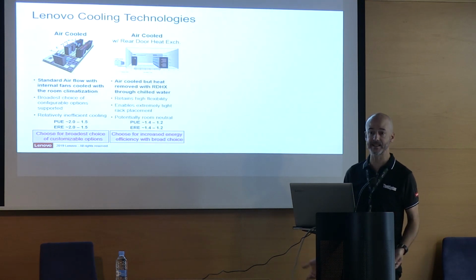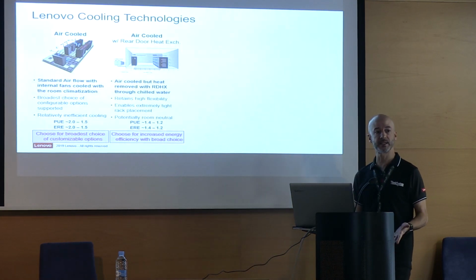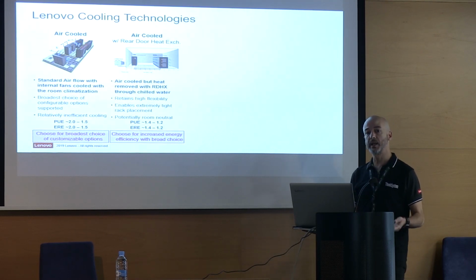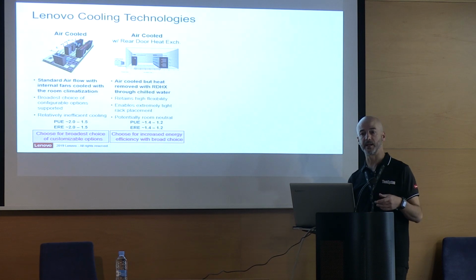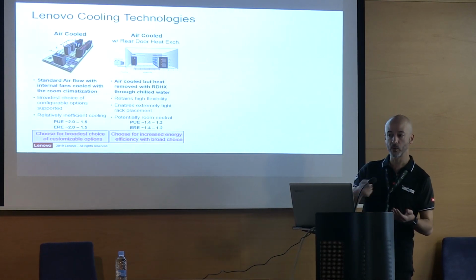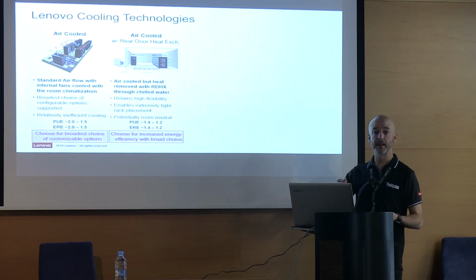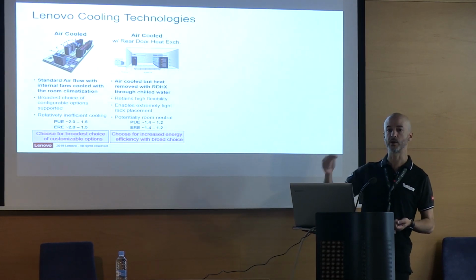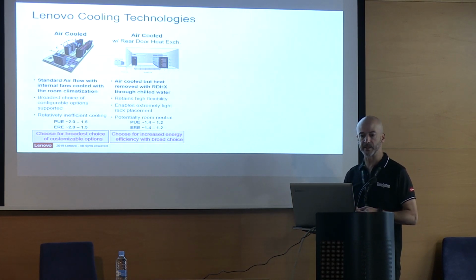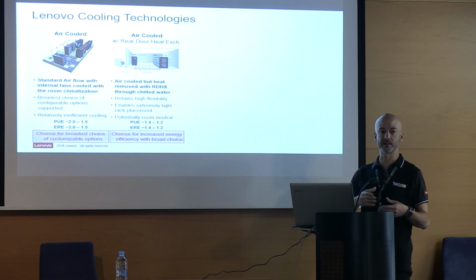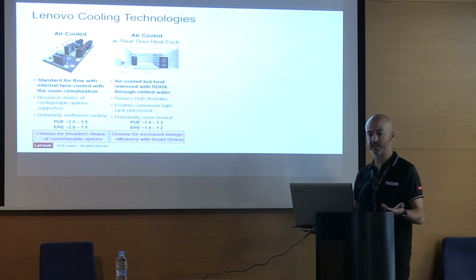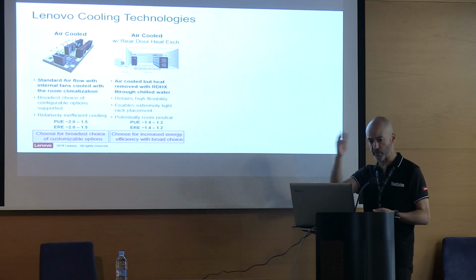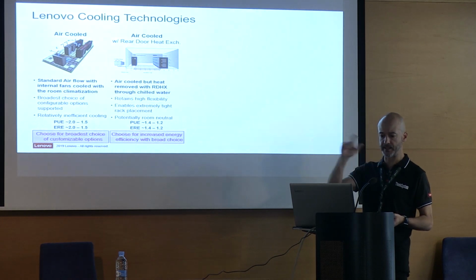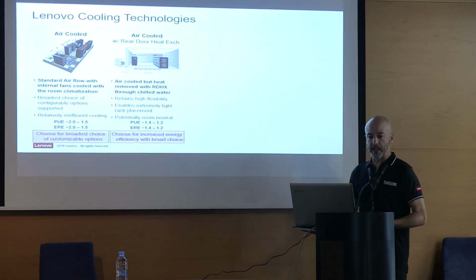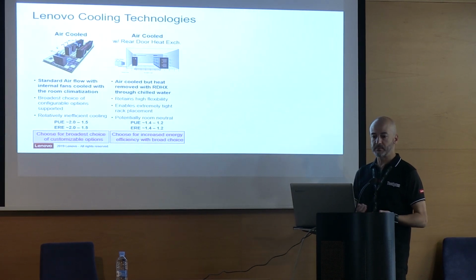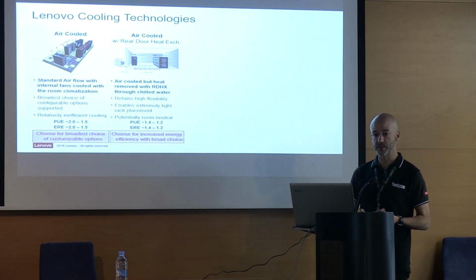The next step beyond traditional air-cooled systems is to provide rear door heat exchangers. That means installing in every rack's rear door a water loop, a water coil that cools the hot air coming out of the machines, so that the air going to the hot aisle is already cold. This is the approach that, for instance, Barcelona Supercomputing Center is following traditionally - the same approach as air cooling, but much more efficient.